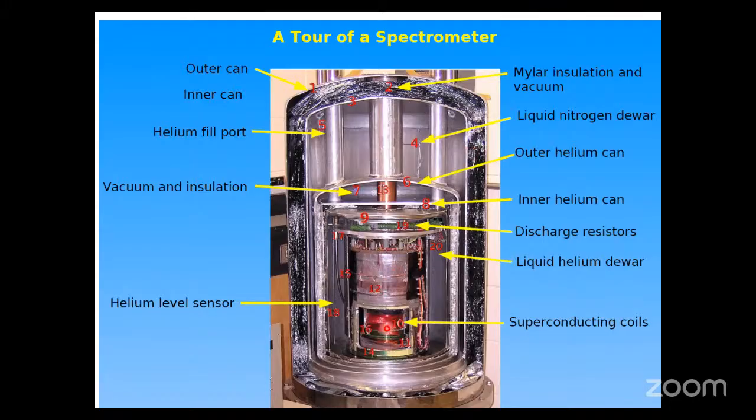Okay, and here somewhere we have the console of that NMR. So we are dropping our NMR tube from the top of this instrument, and it comes over here. Okay, so the main function of this superconducting coil is to give a very high magnetic field. Then here at the console we have the radio frequency, which will be able to give the transitions.